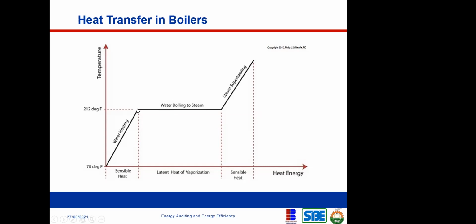So from this point to this point, you're still applying heat, but the heat you're applying at this point is known as latent heat, not sensible heat any longer, because at this point change of phase is happening. From here, it's now fully gas, which is the steam that we want. So this is what is actually happening in a boiler. We apply heat to change water from liquid phase to gaseous phase. That's exactly what is going on in a boiler.